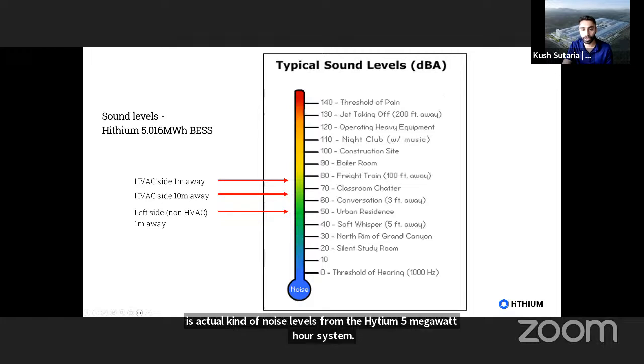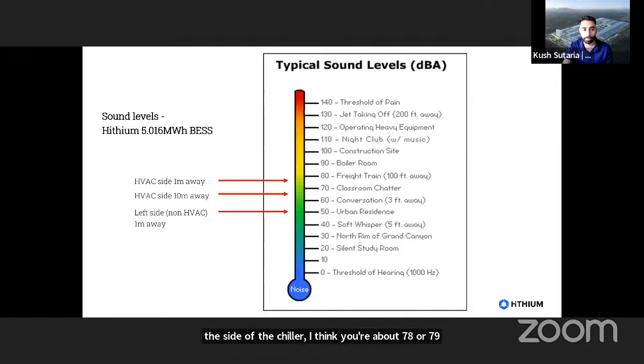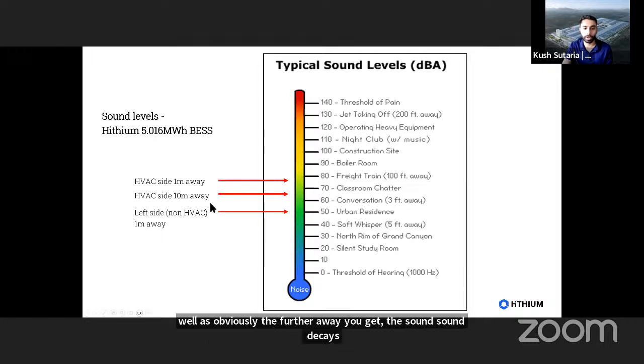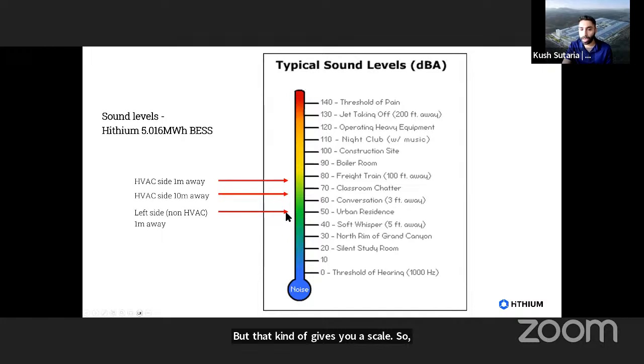1 meter away from the side of the chiller, you're about 78 or 79 dBA. This is very directional as well, so if you're on the left side, not facing the chiller, the sound is drastically reduced, and the further away you get, the sound decays. That gives you a scale. 1 meter away on the non-HVAC side, you're really at about ambient noise of an urban residence. But on the side with the chiller, it can get very loud, to the point where you'd have to shout to talk to each other.